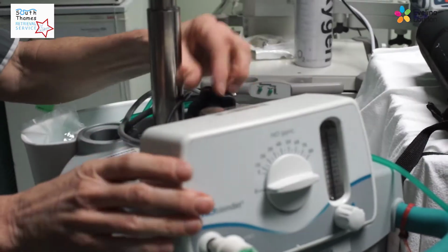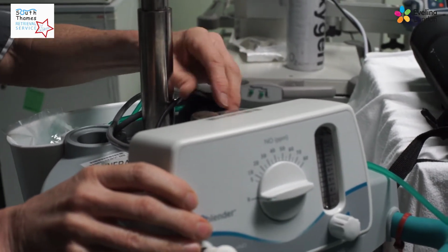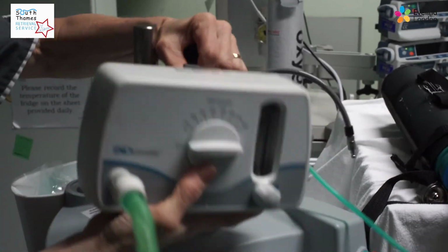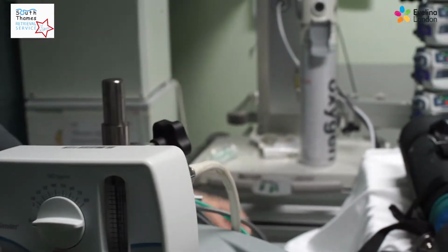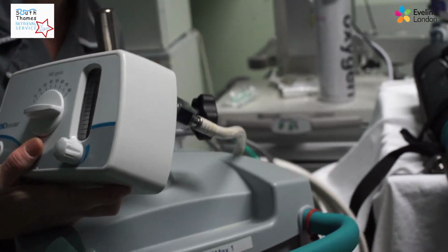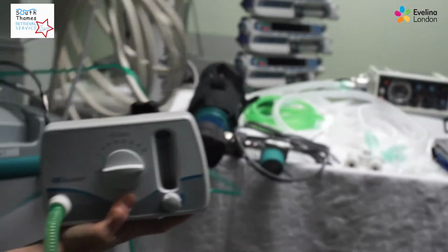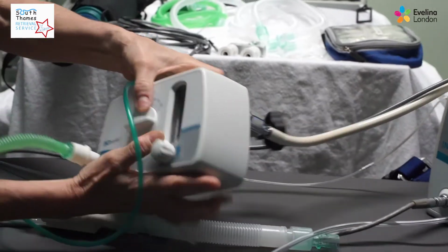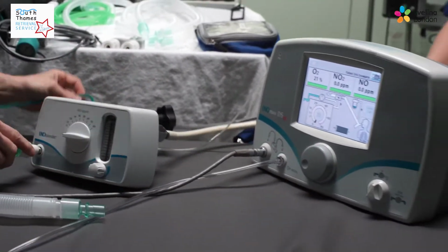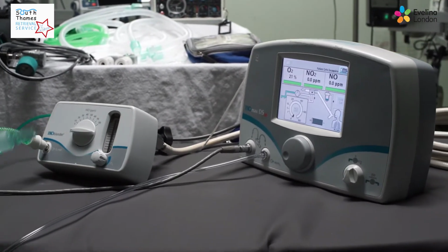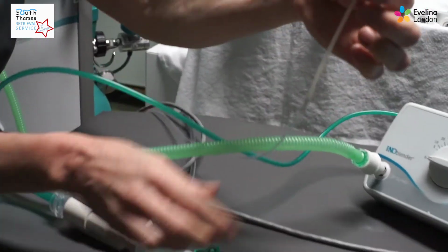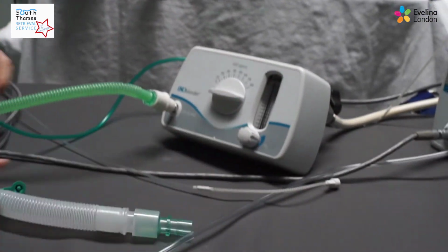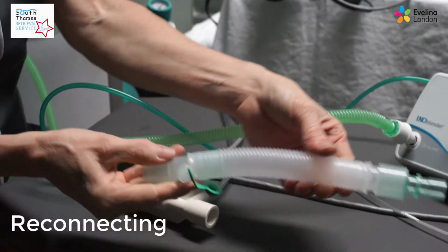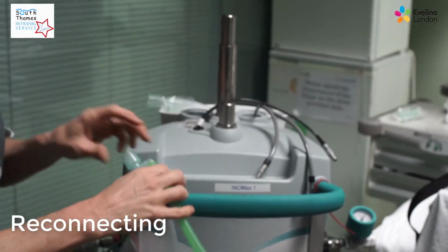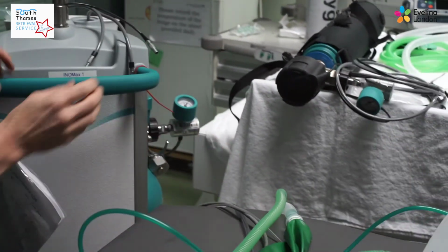So now you want to disconnect the actual blender from the stand, and again you just have to untwist the clamp and then you can lift it up, and attached is still the nitric oxide cable, the hose, so you need to carry that across as well. And then the final thing to do is disconnect the actual nitric measuring lead from the plastic corrugated tubing, and that can be left here with the monitor. So now you're completely disconnected and you can work on setting the nitric up from here.